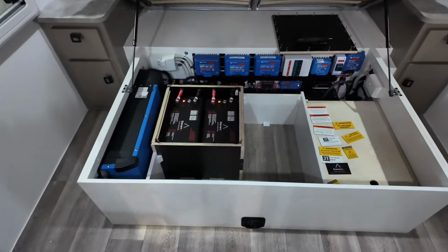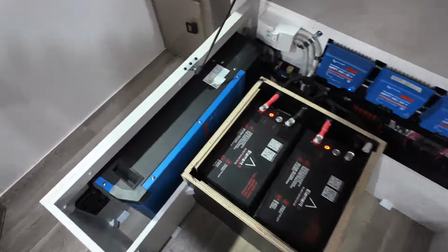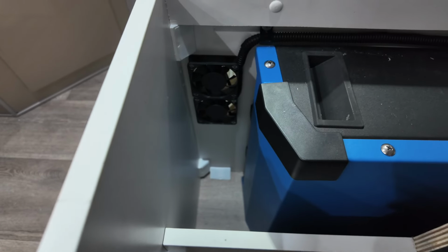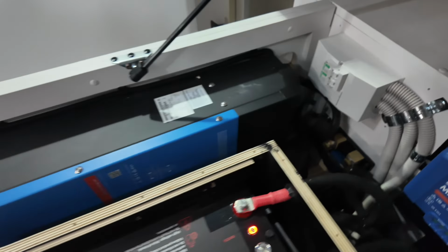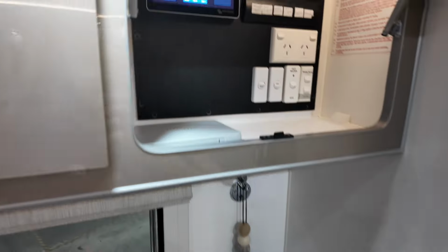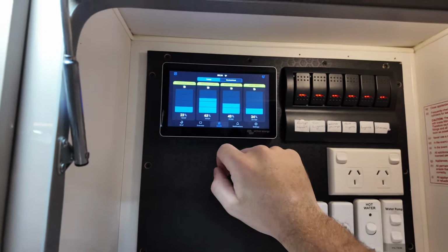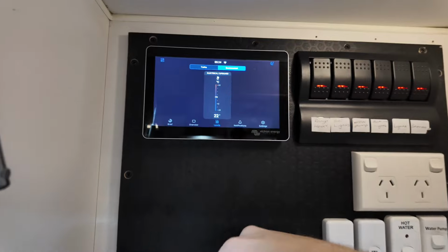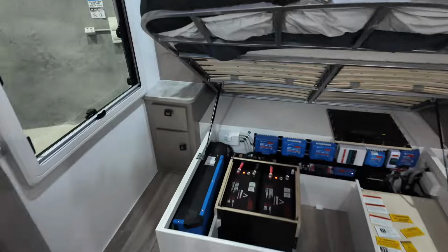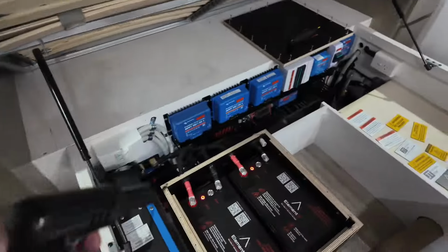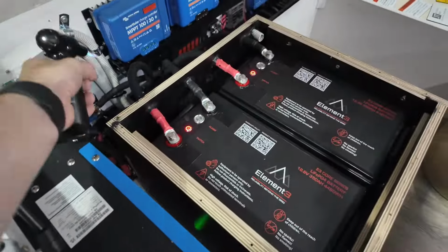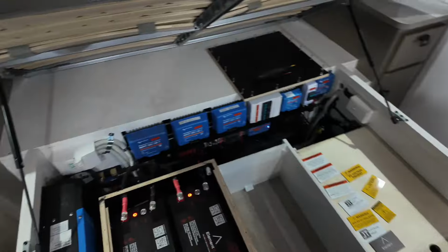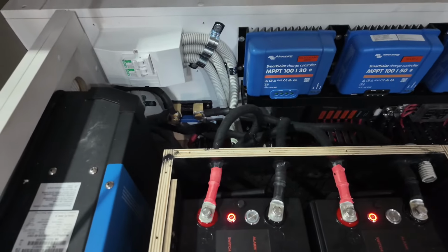Again, people are going to say, oh, under the bed, a lot of heat. What we've done is put 2 fans here and a vent over here, but these are automatic fans, controlled by the electrical cabinet temperature sensor. It's at 22 degrees at the moment. I'm going to get this heat gun and point it at the temp sensor to get it to heat up a little bit. And now, because I've heated it up, the temperature sensor has kicked in and these fans are on.